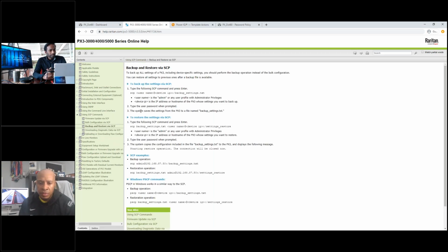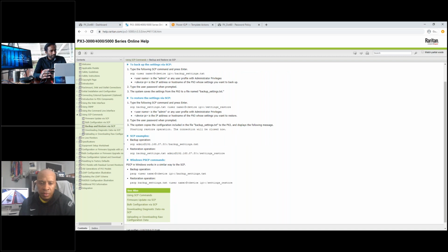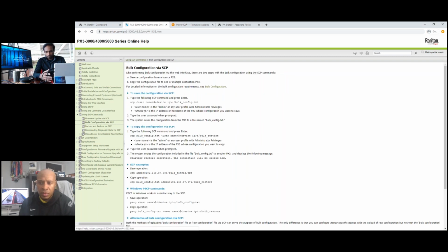So the recommended way, if I were to summarize the different ideas that you mentioned, you would have a limited number of users at the PDU level. You don't want just one, you want more than one, but not too many, because then managing them becomes an issue at the PDU level if you have many PDUs. So you have more than one user at the PDU level, then you have everything pointing to Active Directory for other users. And if you have PowerIQ, you have that pointing to Active Directory as well.